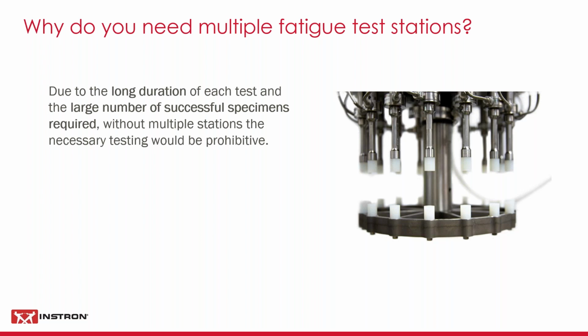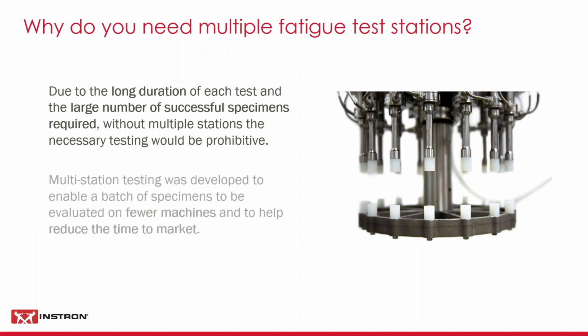So I think I've really covered this slide already in terms of the need for testing multiple specimens in parallel. What you can see here is what you might call the business end of a stent testing carousel, which will accept 16 specimens in parallel. And that's really what I mean about not using one machine per test. So this is really the way that you speed up the test throughput.